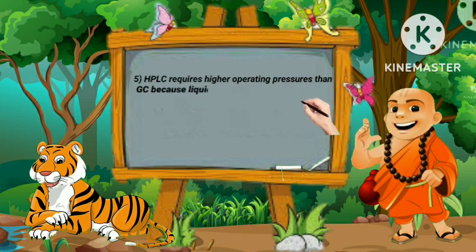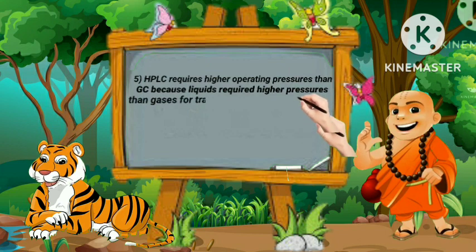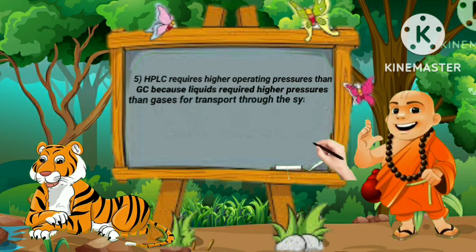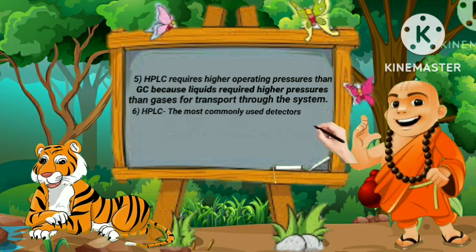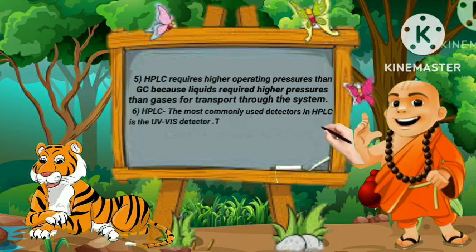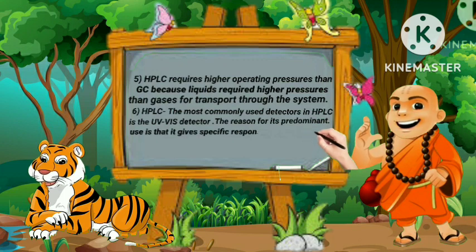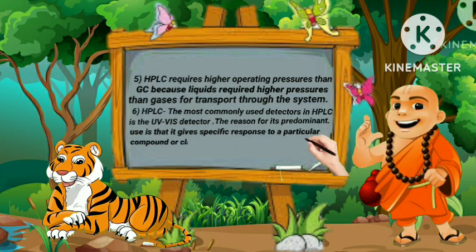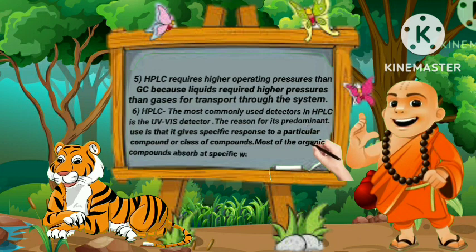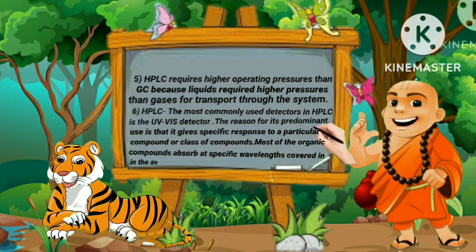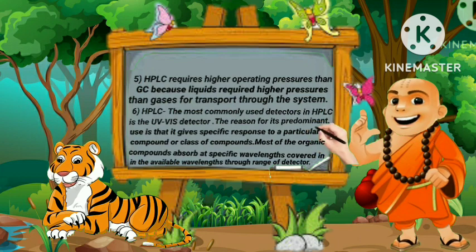HPLC requires higher pressures than GC because liquids require higher pressure than gases for transport through the system. Sixth, the most commonly used detector in HPLC is the UV-visible detector. It gives a specific response to a particular compound or class of compounds, as most organic compounds absorb at specific wavelengths covered in the available wavelength range of detectors.